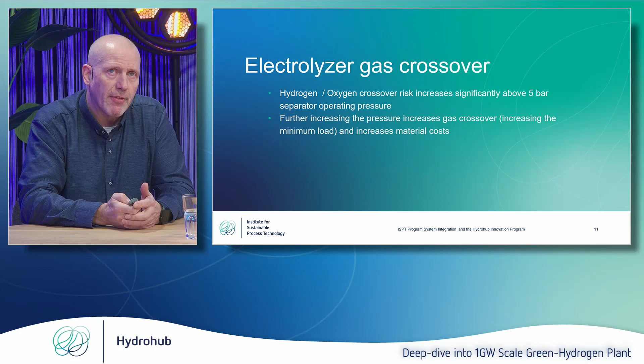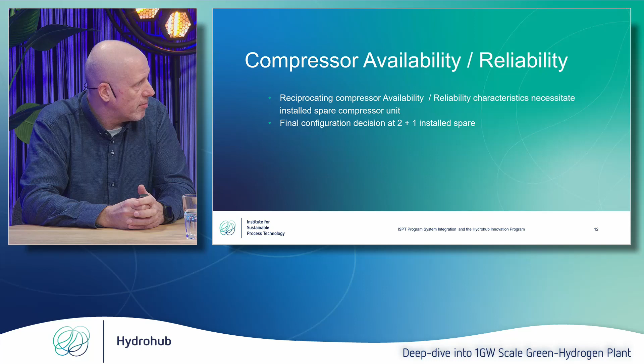And I think that's the last slide I have here. If we would select this reciprocating type of equipment, there are reliability and availability parameters which would then push you to have an installed spare, which may not be the case if you would select centrifugal equipment, always depending on the requirement you have for availability and reliability. So that's where we landed at 2+1 installed spare units.